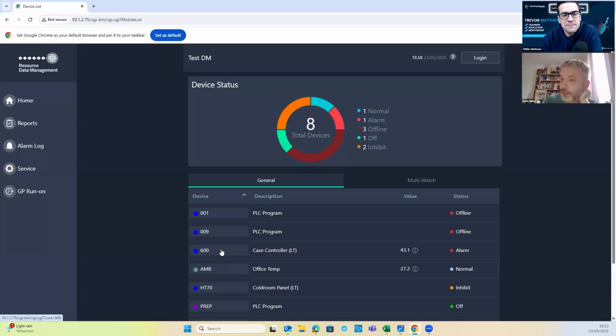The moment it sees it on the network, it will ask the controller for a type file so it knows what to do. It will then load the type file and your controller will appear on there. On the front of the controller, the green light for network will go solid and it will say I'm logged on. So that's happened on that device.